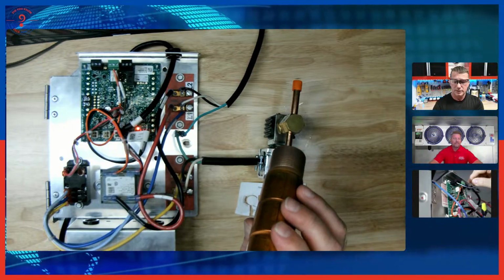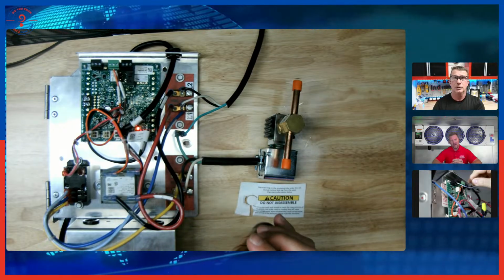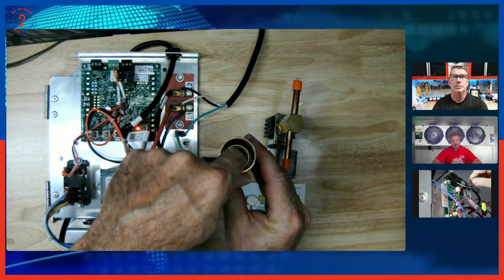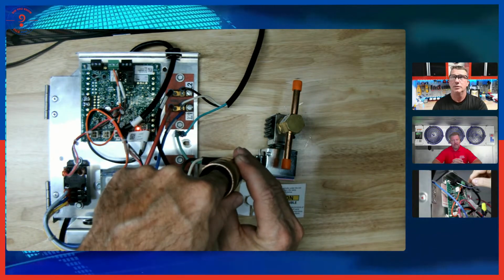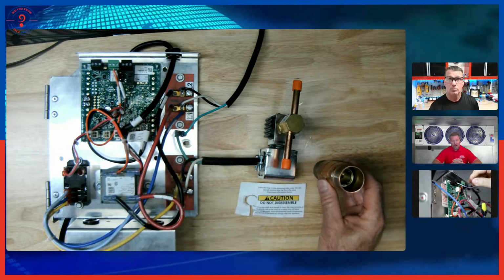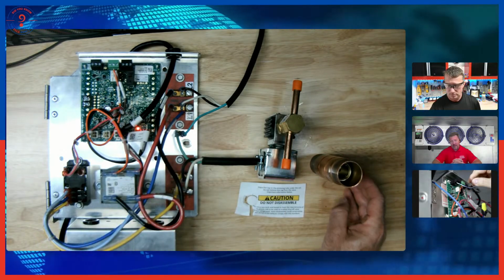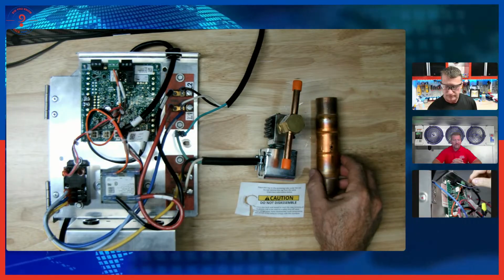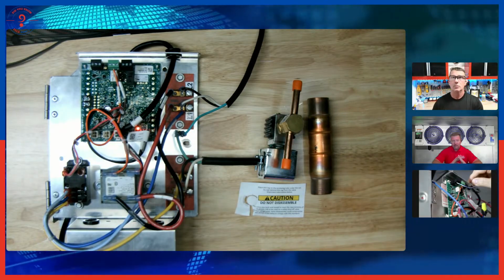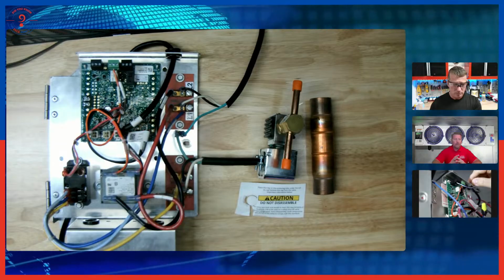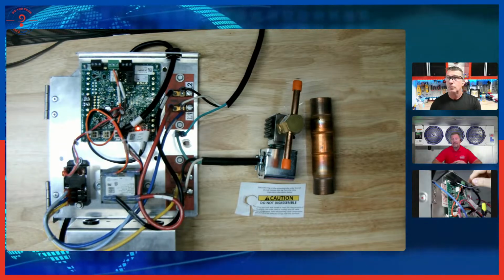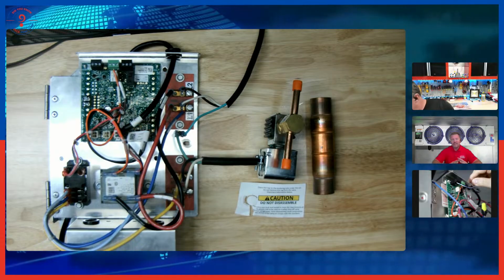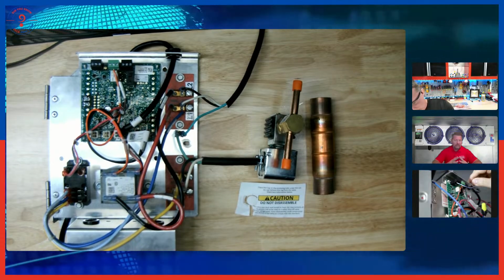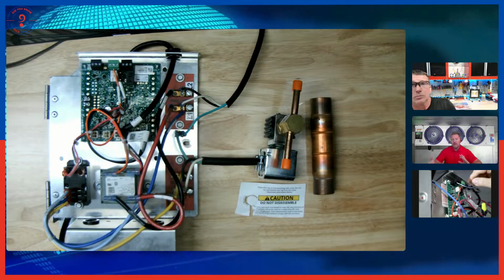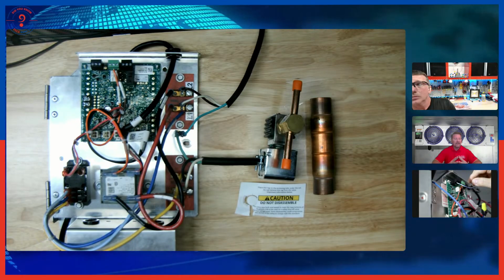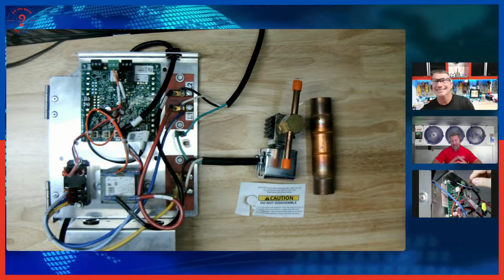Yeah, and I noticed a very minimal amount of pressure to actually activate. I don't know if we can see it, to be able to activate the check valve. And these check valves are not just a generic check valve either. These are A2L specific. They have been spec'd for that. UL recognizes them for that. So it is important for us to stress that this isn't just any old check valve and any old solenoid. Sure. We still do need to use the correct parts for this. I mean, we are talking about a safety device here.